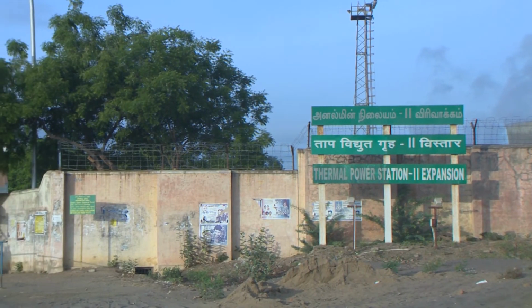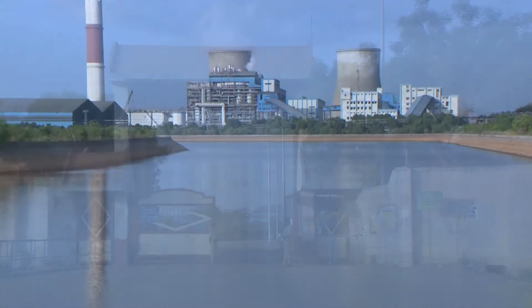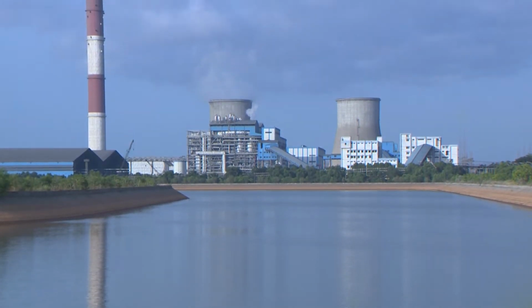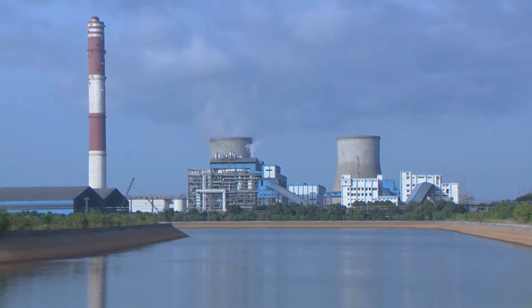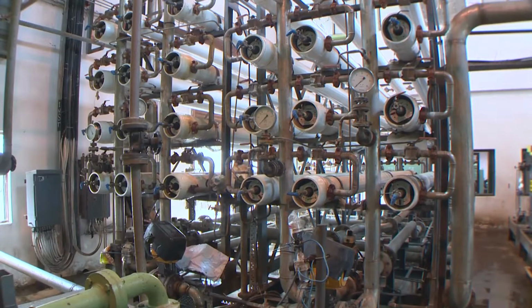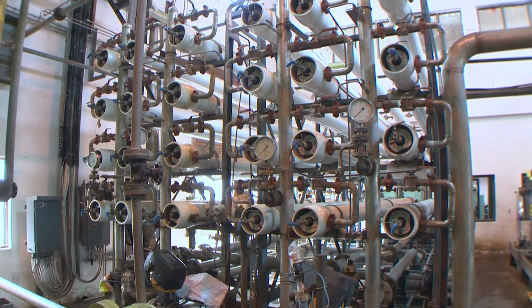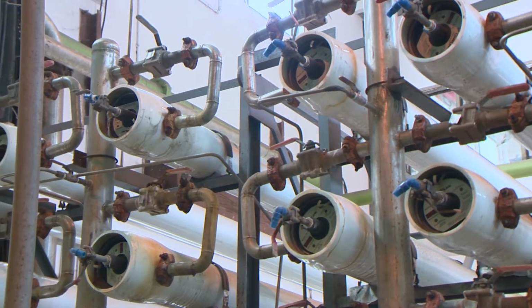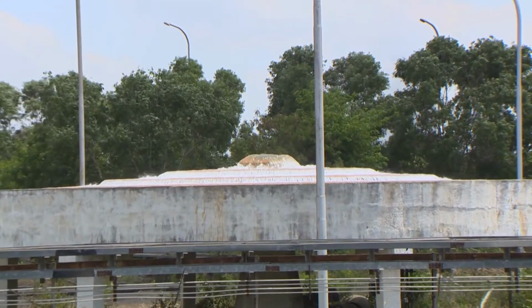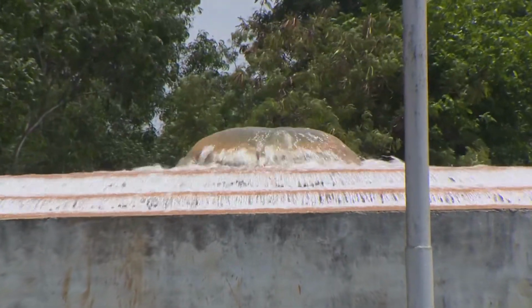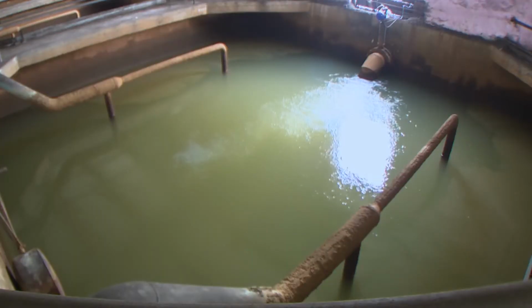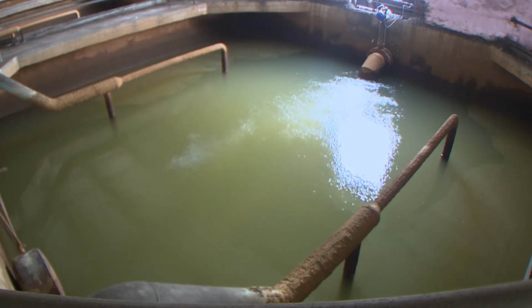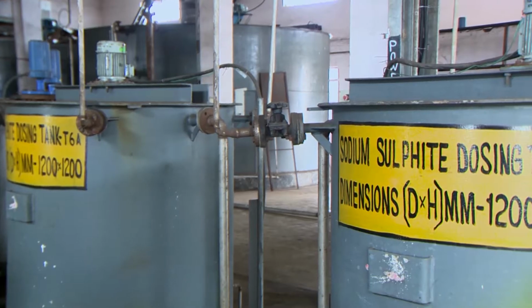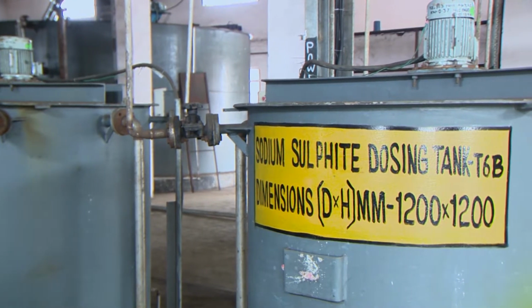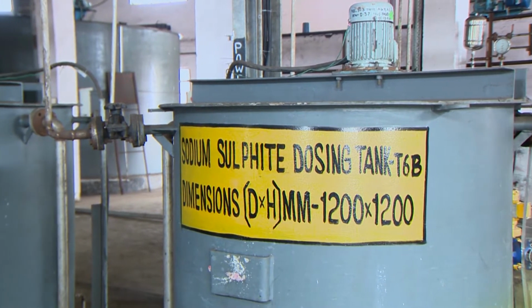In Thermal Power Station 2 expansion, instead of borewell water, stormwater from mine 2 is used for producing DM water, and reverse osmosis process is introduced before ion exchangers. The raw water is treated in an aerator for the removal of iron present in raw water. Then it is sent to pre-treatment plant to produce clarified water. The main clarifier water is used for circulating makeup water system.